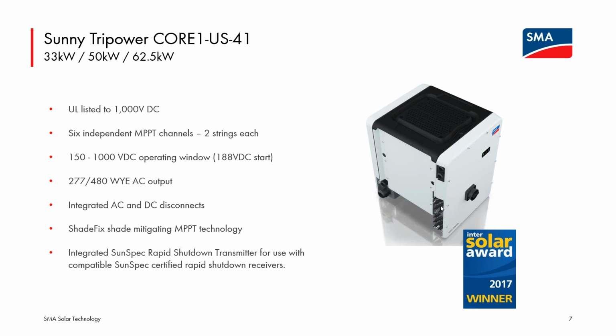There are 12 direct string inputs to each and every CORE1, all 3 power classes. The way those inputs are architected to come into the power conversion electronics of the inverter is there are 6 independent tracking channels with 2 string inputs for each of those 6 tracking channels. The inverter manages each of those 6 inputs independently. So in essence, it's as if you're getting 6 inverters in each box.